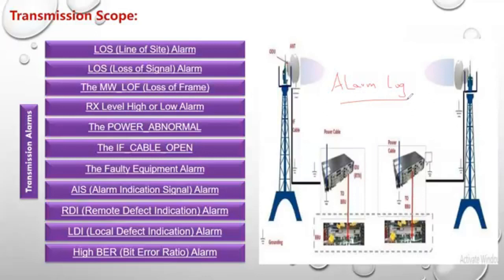I just want you to know what problem caused the fluctuation and then was cleared. I have to access this microwave by using my laptop and access the indoor unit by the control card or management card that we talked about. Then I take or download the alarm log from it so I can see all the alarms with the signs and everything as well.